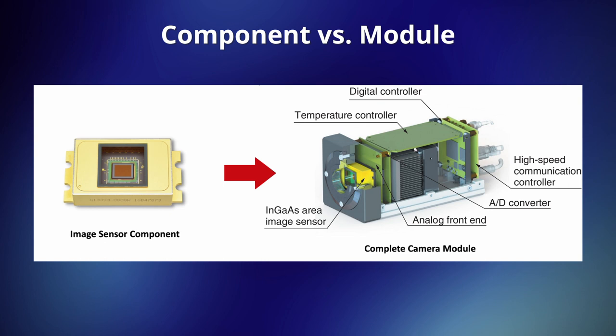Hamamatsu makes all kinds of image sensor chips — CMOS and CCD for UV and visible light detection, and InGaAs image sensors for IR detection. With a single sensor chip alone, you can't acquire image or spectrum data because the image sensor is a photodiode array operated in integration mode. Timing control, readout electronics, bias voltage, and digital signal processing circuits are all required. Any feature added around the sensor chip could be part of the module solution.